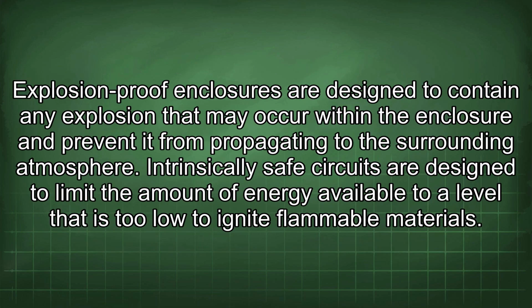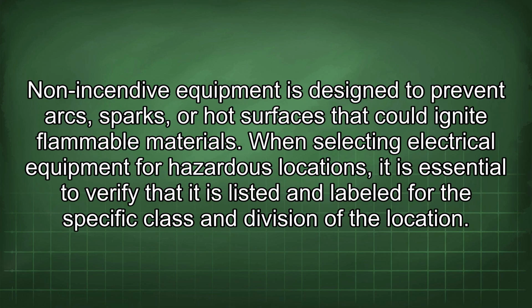Explosion-proof enclosures are designed to contain any explosion that may occur within the enclosure and prevent it from propagating to the surrounding atmosphere. Intrinsically safe circuits are designed to limit the amount of energy available to a level that is too low to ignite flammable materials. Non-incendive equipment is designed to prevent arcs, sparks, or hot surfaces that could ignite flammable materials.